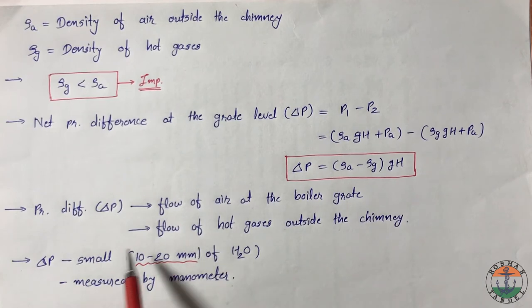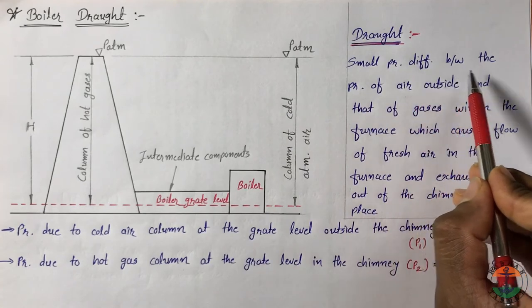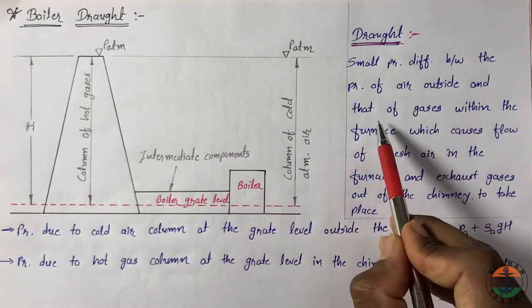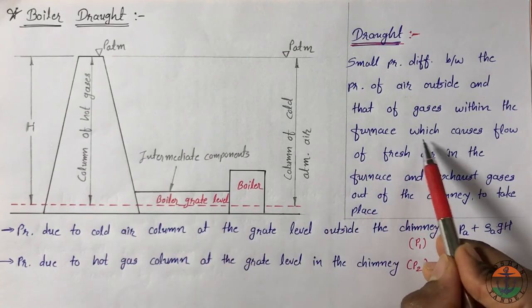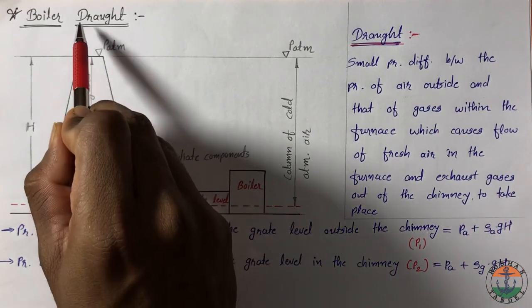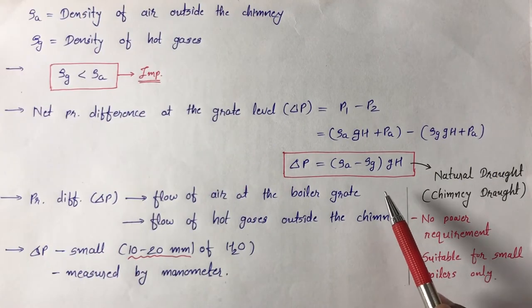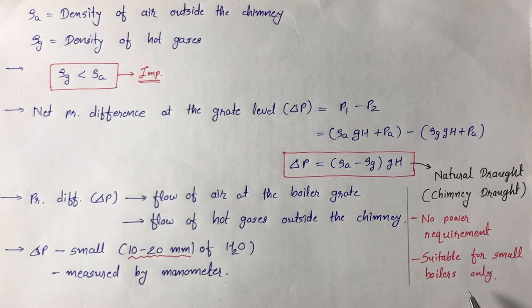Its value is very small and it is measured with the help of a manometer. Draft is defined as a small pressure difference between pressure of air outside and that of hot gases within the furnace or chimney portion, which causes flow of fresh air into the furnace and exhaust gases out of the chimney. This natural or chimney draft requires no extra power and is used only in small capacity boilers; it is not suitable for large power plants.